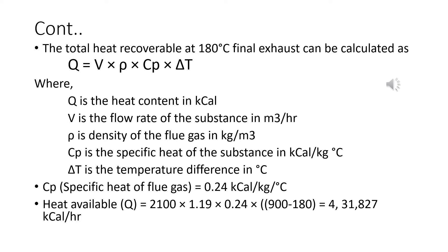Cp is the specific heat of the substance, also a constant value of 0.24. Delta T is the temperature difference — it is already mentioned that the exhaust is at 900 degrees Celsius, so delta T will be 900 minus 180 degrees. V has been given as 2100 cubic meters per hour.